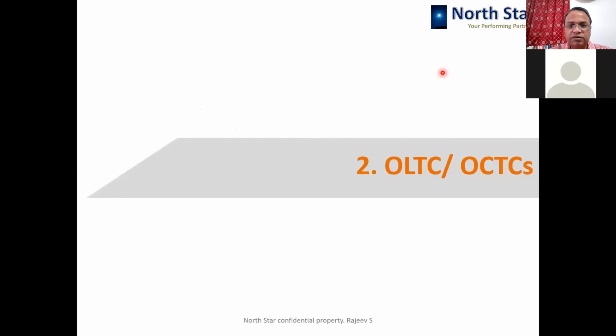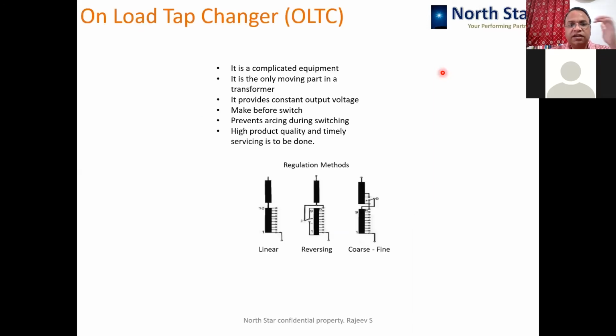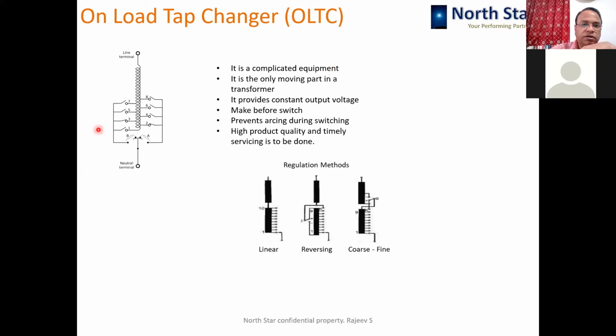Now coming to OLTCs, on-load tap changers are devices which are very complicated equipment. Okay, it is the only moving part in a transformer, and it is put on the transformer to get a constant output voltage. So it is a make-before-break switch. You can see this in the circuit, how it is operating. Before this moves, the circuit is already completed in some other contact, and the previous contact gets opened. So this is how the make-before-break arrangement works, so that at no point of time the circuit is being broken. So the continuity of the power is maintained by this arrangement.